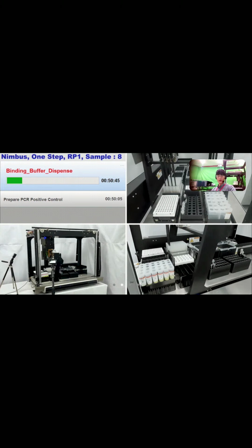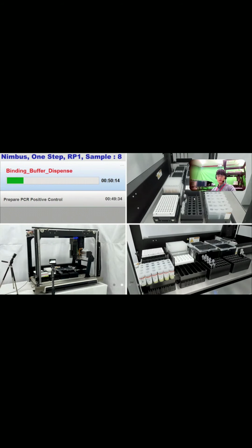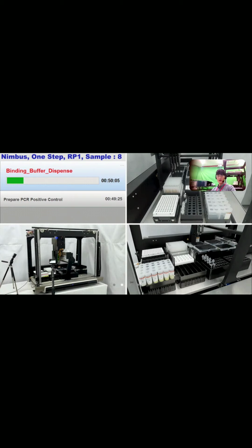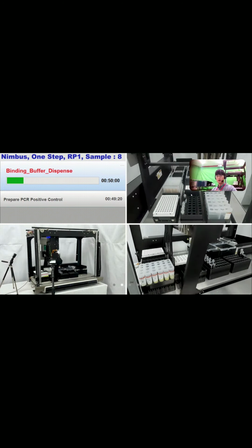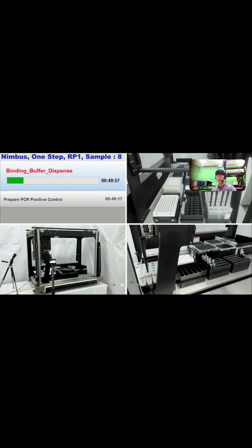From the binding buffer, wash 1, 2, 3, and elution, they're gonna use the CLD when the machine aspirates each liquid from the tube 2, 3, 4, 5, 6. And also at this moment, when they aspirate IC, PK, bead, sample, you need to check the XY positions, that each tip is positioned on the center of each well. IC, PK, bead, sample or this tube.